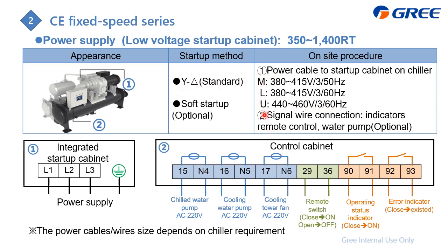The second part is this, which connects to the optional wiring, including the indicators, remote control, or the water pump. Just connect to it so you can allow this centrifugal chiller to be controlled, or it can display the error or the operating data. As for the startup method, you can select star-delta, which is the standard, or you can choose the soft startup method, which is optional.